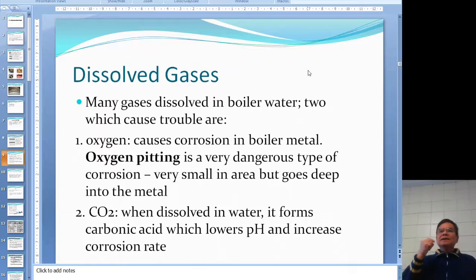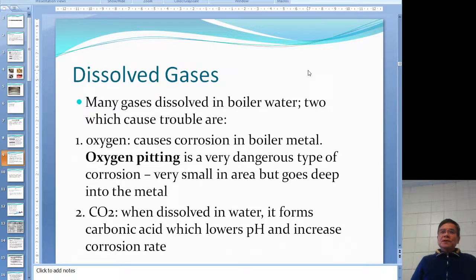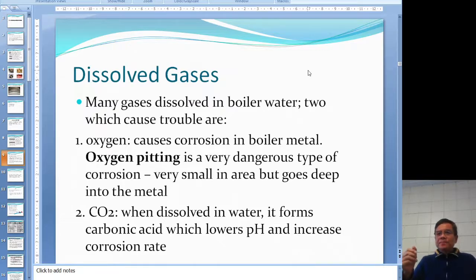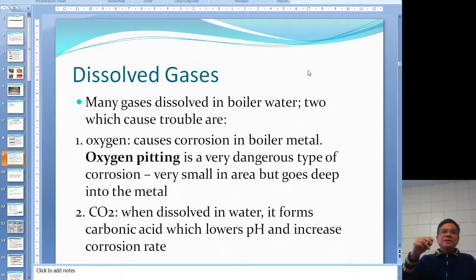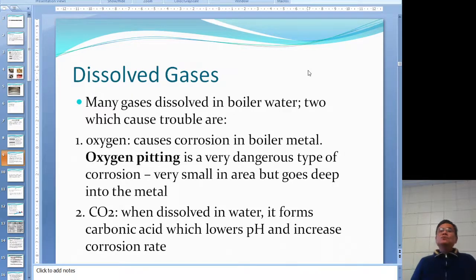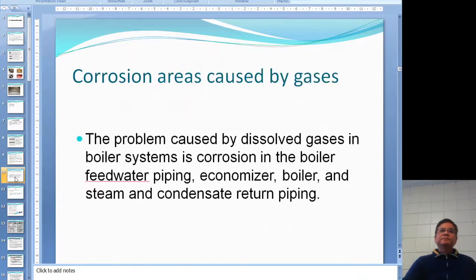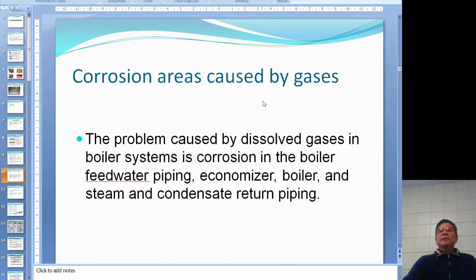The other dissolved gas we care about is CO2. CO2 combines with water to form carbonic acid, H2CO3. Any type of acid lowers the pH, and as the pH decreases, the corrosion rate increases. So those are the two dissolved gases we need to remove.